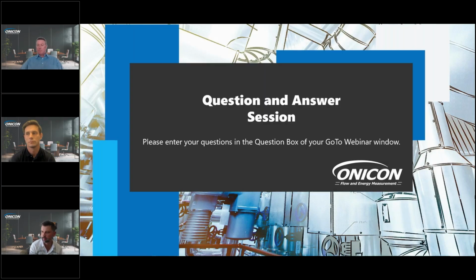All right, thanks, Scott. Another good question. This wasn't in regards to our System 1000, but what is the life cycle of the new immersion sensors? I'm assuming that was in regards to our new insertion mag meters. So we've been selling insertion meters since the beginning of ONICON's time. Back in the 80s, we had insertion turbine meters. And even insertion turbine meters with moving parts, we've had meters come back after 20 years. And if it's in a clean, closed loop system with well-treated water, those meters have worked after 20 years and still working great. For the mag meters, we've been selling the insertion mag meters for over 20 years. Kind of same case here, still working great.